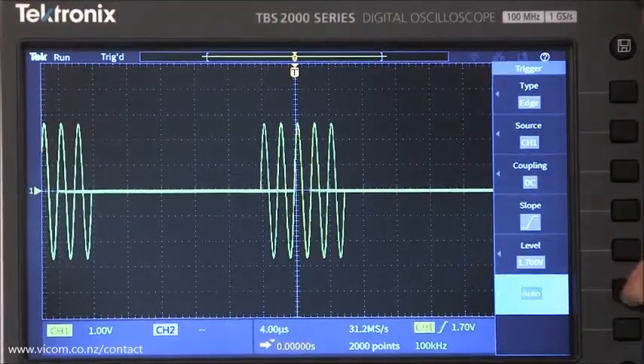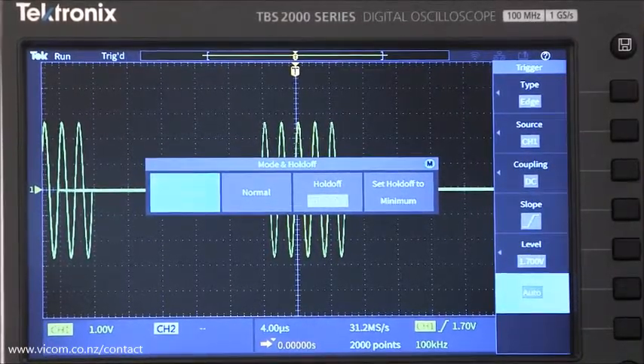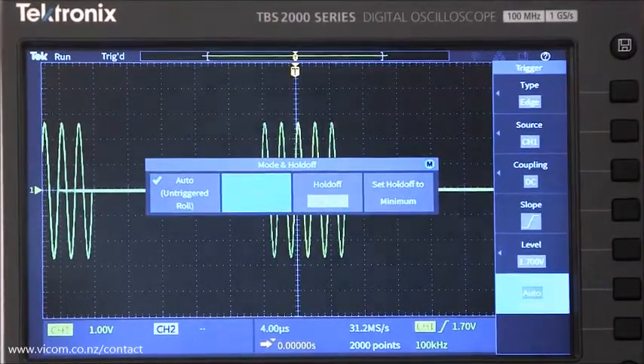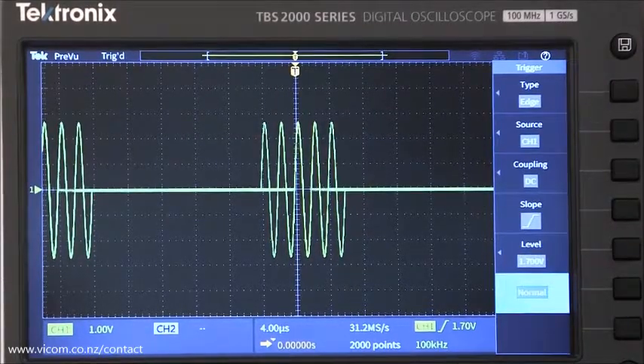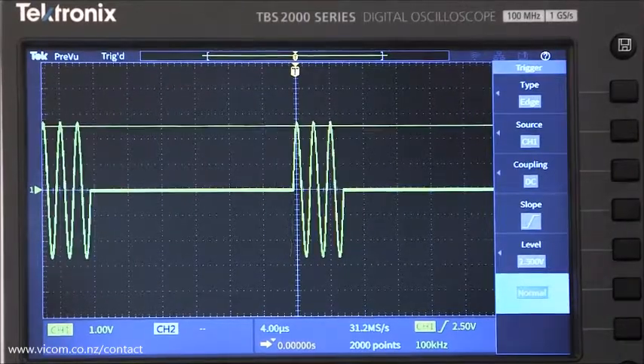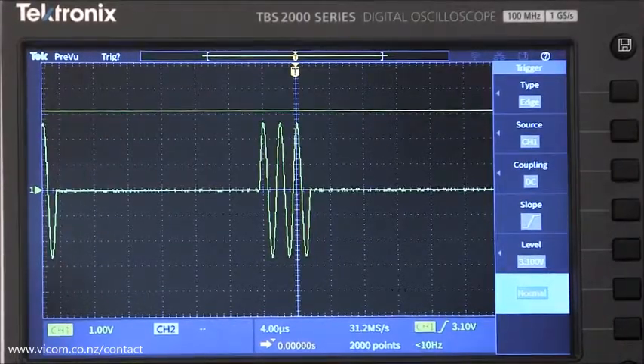The other trigger mode is normal mode. It's a little counterintuitive, but normal mode is not the default setting. When the trigger system is in normal mode, the scope acquires a waveform only when the trigger condition is met. So as you can see, when I lift it, it's no longer triggering.